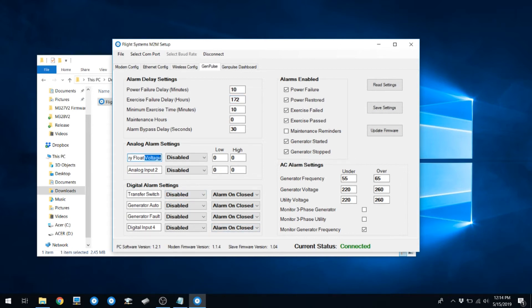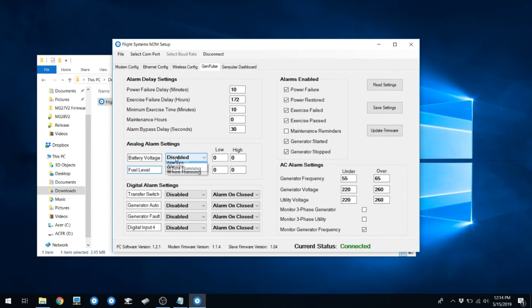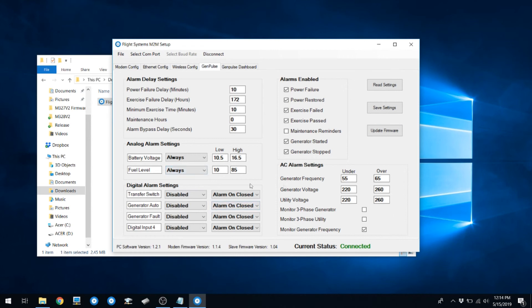You should also set labels for your analog channels to give them descriptive names for what they're actually measuring. In our case, we'll put battery voltage in analog one, and analog two will be fuel level. Make sure to set these to always, and put in a reasonable value for your under and over voltages on your battery. Let's set up our fuel level like we're monitoring an LP tank. We'll set our low at 10% and our high at 85%. We're going to set this to always instead of just while the generator's running.